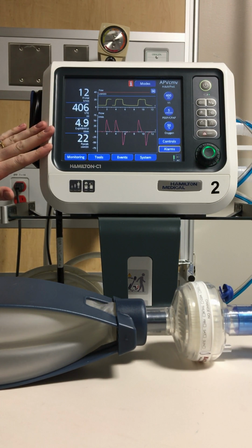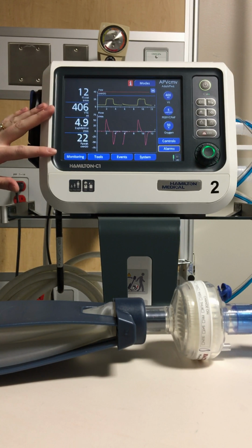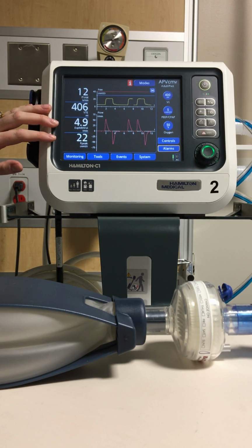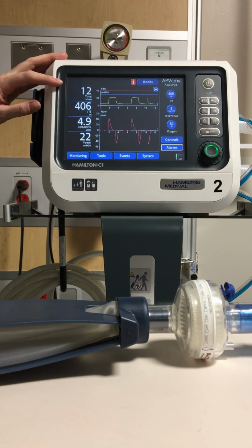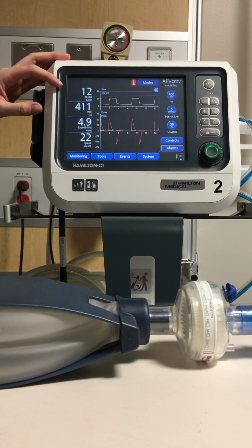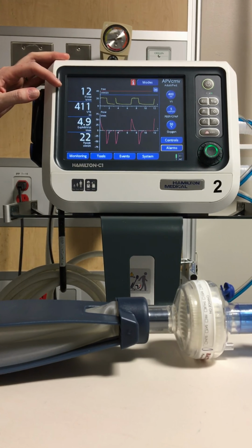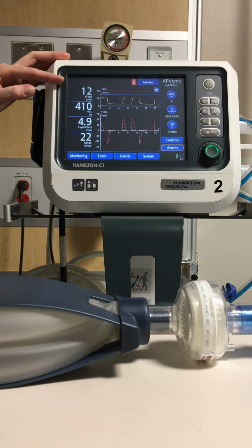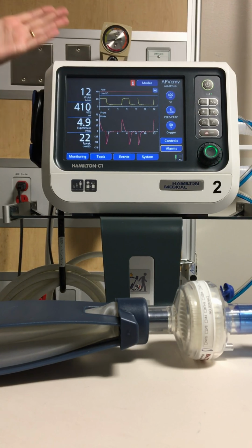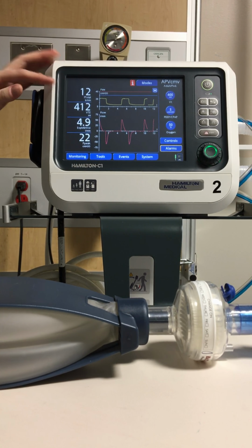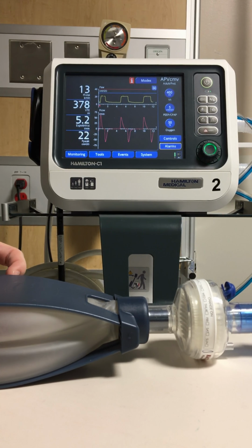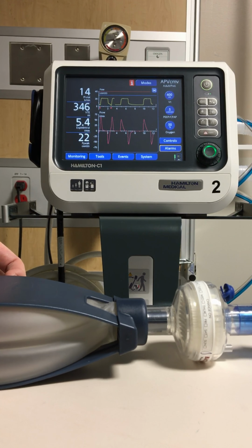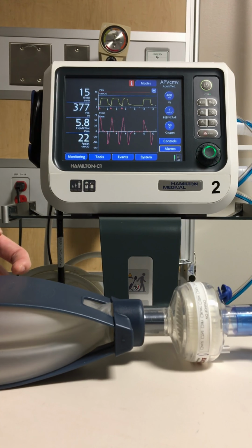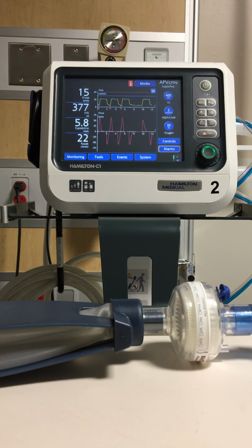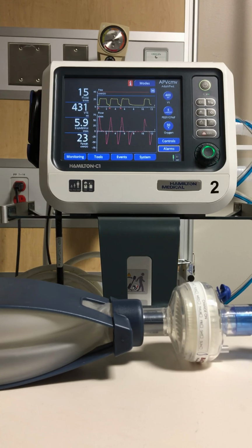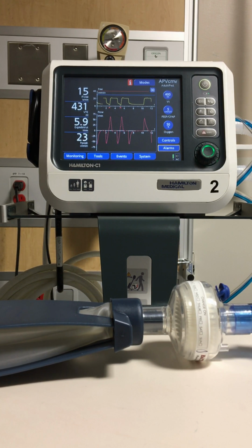On the left side of the screen, if you're looking at it, are the monitored values, just the most common monitored values. So the top one is the respiratory rate. It says F total, F meaning frequency, so how many times per minute the patient is breathing. It's currently 12, which we have it set to at the moment. If your patient had effort, and I will demonstrate that, that number will increase to whatever the patient is actually receiving for breaths. And now when I don't trigger the breath anymore, it will slowly come back down to the 12.